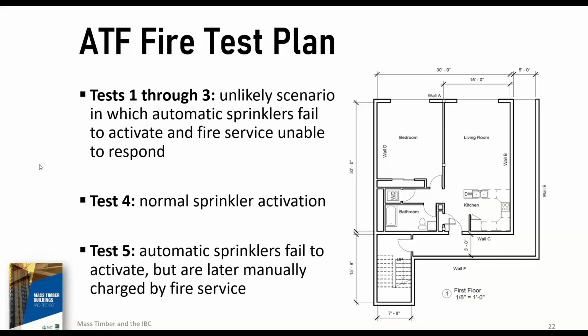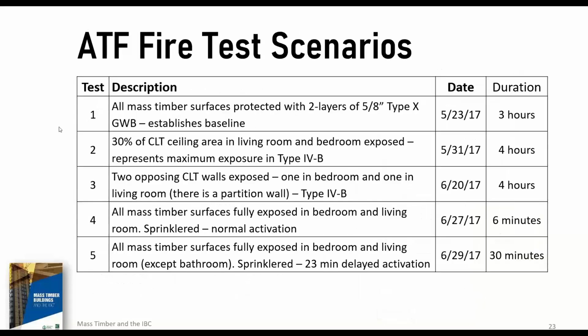Test number 4 is a normal activation of one sprinkler head at a point source fire, in this case the kitchen. We'll talk a little bit about the location and the testing configuration there as well. And test number 5 was to simulate a failure of the sprinkler system to activate and having to be manually charged by the fire service through the standpipe or riser. So we'll take a look at that now.